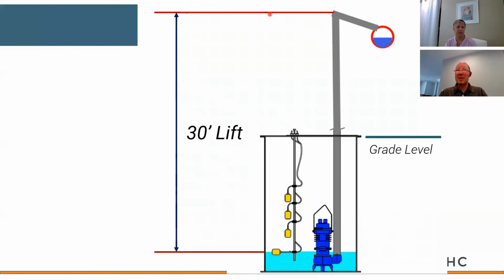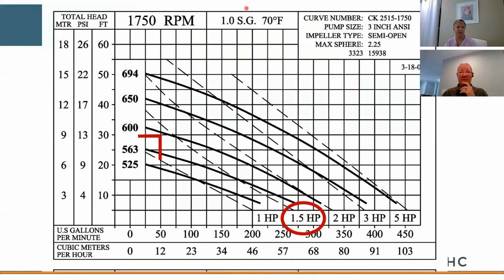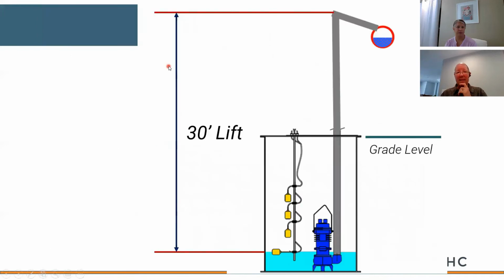Now, if you consider non-overloading, you're considering riding out on your pump curve. Well, if we ride out on this pump curve, you'll notice we're going to get more flow, but we're also going to get less head pressure. Our open system is requiring head pressure. Meaning, if I ride out on my pump curve to not 50 gallons a minute, but maybe 150 gallons a minute, my lift isn't 30 feet, it's 25 feet. Well, if I need 30 foot of elevation and I'm only getting 25 feet, guess what? I've got water that's stacked in my riser, but it's not going anywhere.